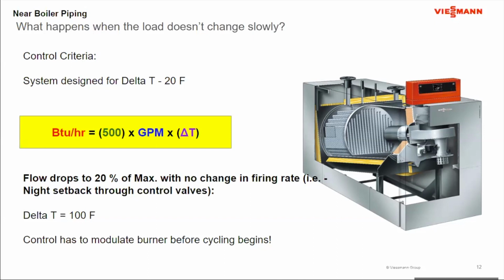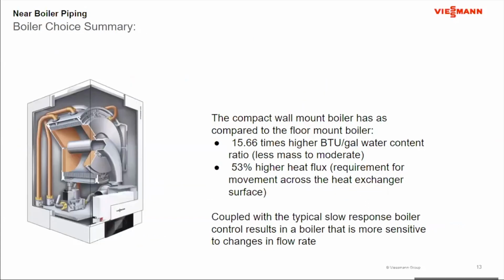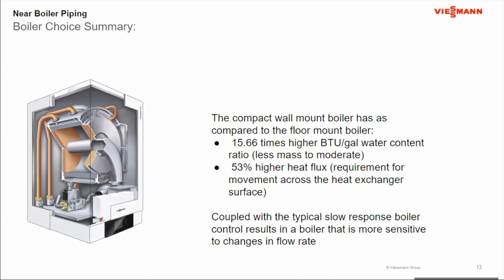Okay, so we have criteria within the controlling of the boiler. There's heat flux. There's also the BTU per gallon ratio, if you will. So how does this all play into the piping of the boiler? Okay, so if I look at a compact wall-mounted boiler and I compare it to a floor-mounted boiler, it has over 15 times higher BTU per water content. So there's less mass to moderate the increase in temperature when there is a change. Additionally, it also has 53% higher heat flux. So there's more of a need to maintain a constant flow across that heat exchanger to pull the heat away from the surface of the heat exchanger.